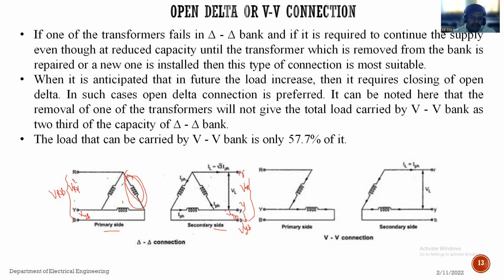When any one winding is burned or open circuited, or any one transformer is taken out for maintenance, the connection becomes like a VV connection, a V-shape connection. This connection is called VV connection, or open delta connection.